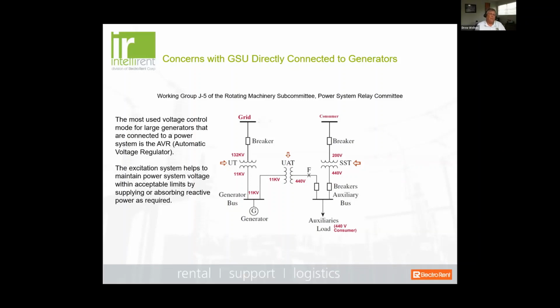Now, the transformers most subjected to this condition are those that are GSUs. And that has a lot to do with failures in the automatic voltage regulation and your excitation system. Remember the other term, overexcited? So what we know is that the generator is directly connected to the GSU, and then you have your breaker, as you see right here. Well, anything that happens to the generator in terms of it coming up online or coming up to speed, that transformer is also going to be subjected to as well, because there's no breaker in between. Sometimes you do have a breaker in between, sometimes you don't, but it's important to understand that if your GSU has no breaker between the generator, whatever happens to that generator is going to happen to the transformer as well.